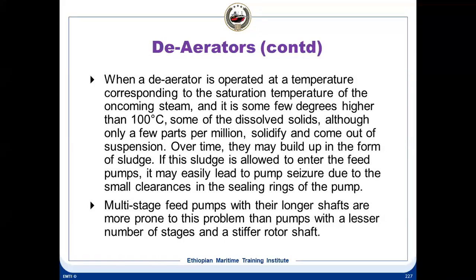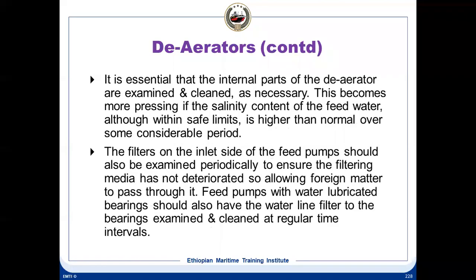And especially for the high pressure pumps, they are normally multi-stage pumps, and they have many impellers fitted on the same shaft, which is a pretty long shaft. With these multi-stage pumps, you can have a bigger problem with these particles, dissolved solids, etc., which come with the condensate. So it is essential that internal parts of the deaerator are examined and cleaned from time to time. And this becomes more pressing if the salinity content of your feed water is higher than normal.